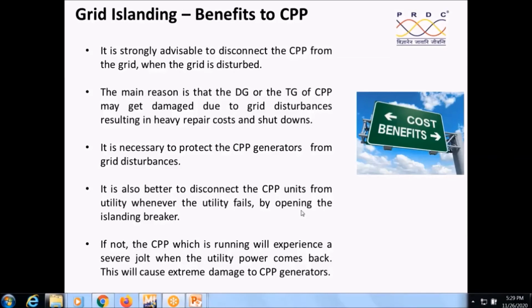And the CPP, if it is not isolated, may suffer extreme damages. So whenever there is a major disturbance, and if we are not able to survive, there can be a major problem to our generators. Therefore, we need to ensure that the CPP gets isolated. Therefore, the grid islanding scheme is going to give the benefit both for the utility and also for the captive power plant.